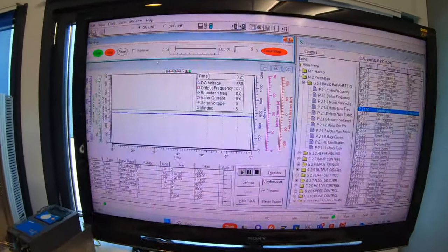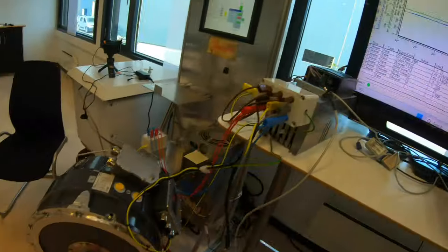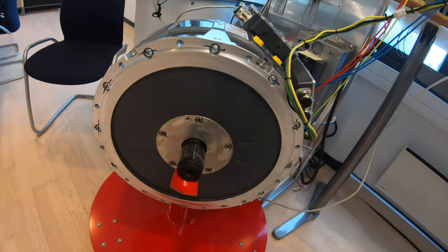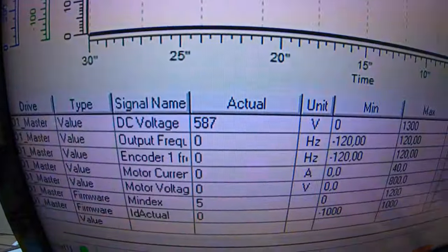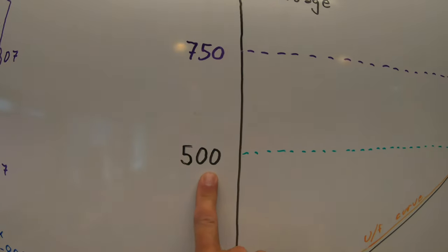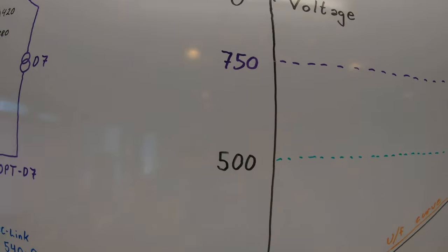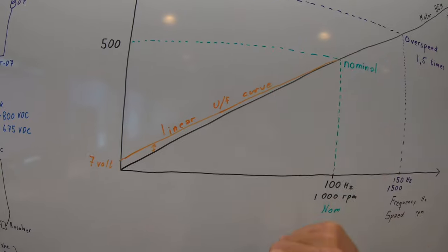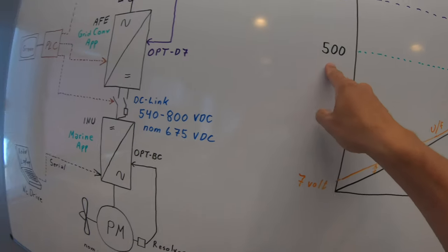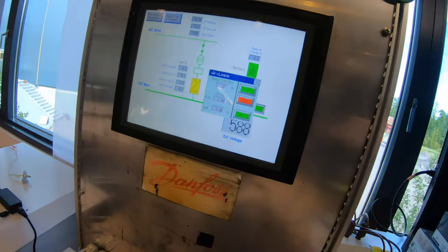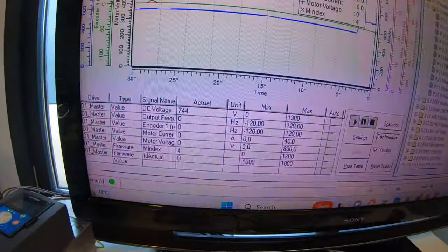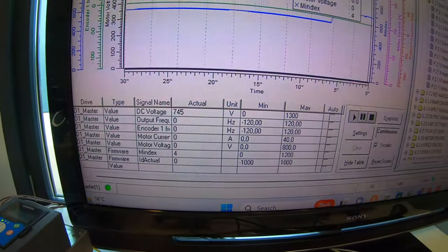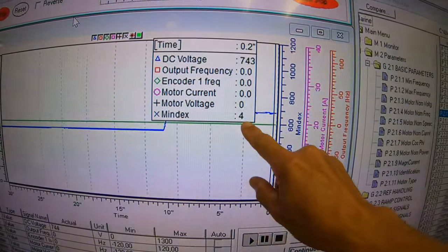We are now ready to run the motor to its nominal RPM. But first thing - mechanical guys, prove it's safe, disconnected, flat pitch, or whatever. Then the DC voltage. DC voltage is now 587V, and that is too small to produce the nominal 500 AC volt which takes to the motor. Relation between DC and AC is square root of 2, so we need minimum 720 volts to produce 500 volts. We start the active front end and it goes to 740 volts. So it should be no problem going to the AC voltage of 500 volts. We see this on the modulation index.